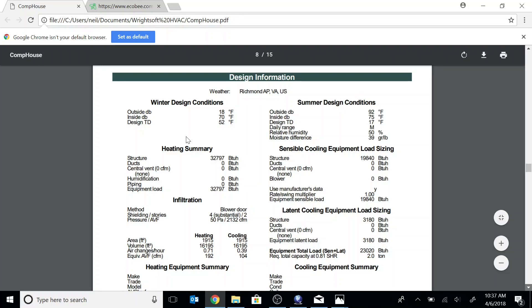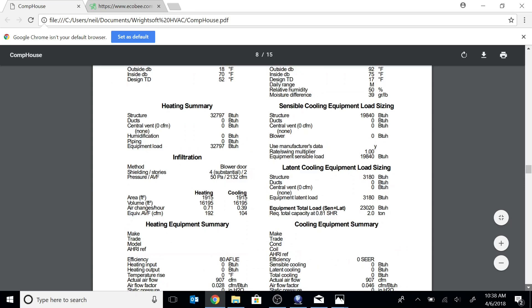This is just kind of everything on one sheet. You can see the outdoor design conditions: 18 degrees outside, 70 inside — this is in the winter — temperature difference of 52, and that is the heat loss. I did use a blower door for the infiltration. I think that's a mistake a lot of designers make — using the standard infiltration rates that Wrightsoft uses. I'll show you that in a minute.